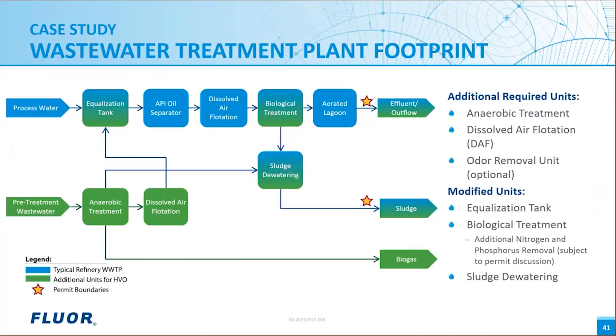Then the equalization tank should be modified for the new hydraulic capacity. Biological units to be upgraded for nitrogen and phosphorus removal if required. And the sludge dewatering units should be modified for the new system. It is essential to minimize sludge production in renewable projects. That is one of the main reasons for anaerobic treatment, along with high concentration. Lastly, odor control. We don't show it on the scheme, but we should mention odor control as a potential issue for renewable diesel projects. And additional odor removal units may be required as well. So all permit boundaries, effluent discharge, and the sludge disposal should be reassessed. And if you zoom in on anaerobic treatment, biogas is the value-added product that we produce out of wastewater.